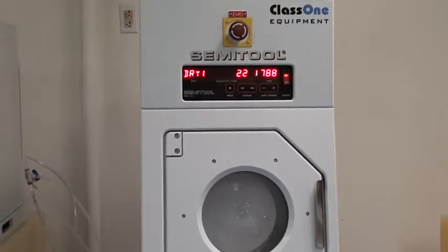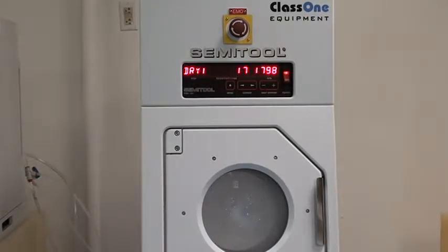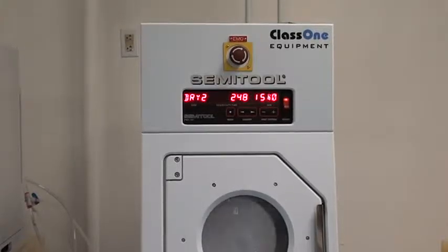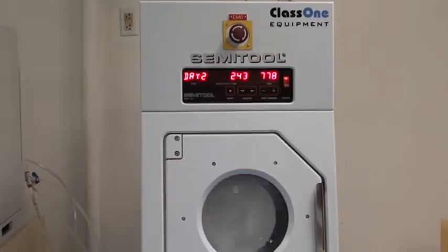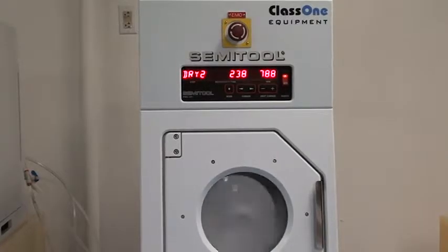Also installed are new solenoid valves, new door seals, new isolation vibration dampeners, new N2 filter, new rear bowl seal. All the nozzles are inspected for spray pattern and functionality. All the delivery lines are replaced, the pneumatic lines are replaced if needed, wiring is replaced if needed. Basically, the system is checked from top to bottom and tested.